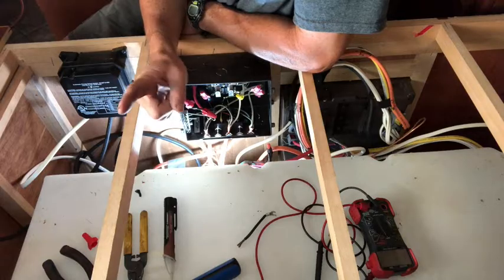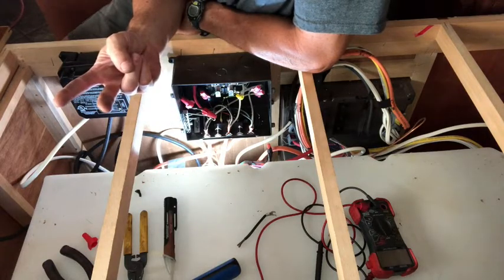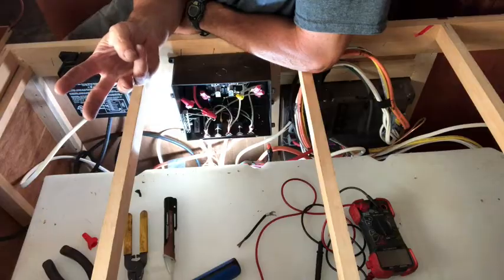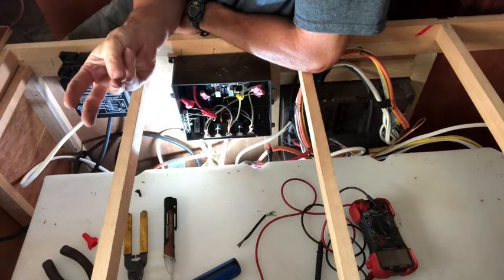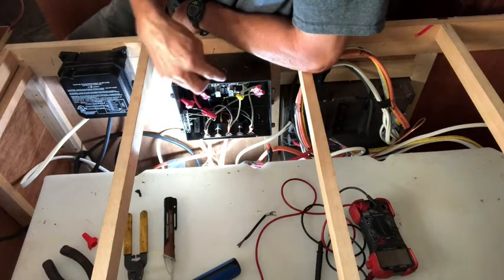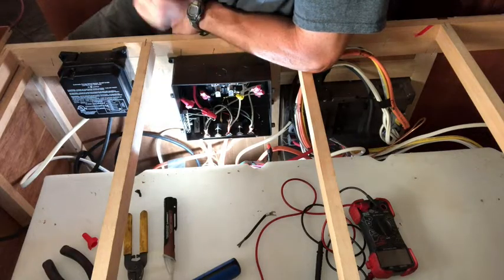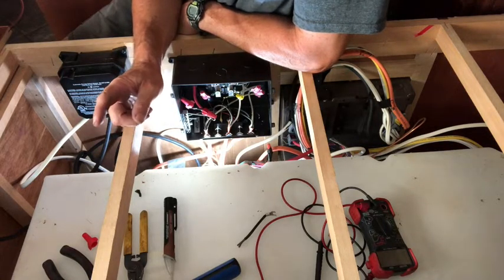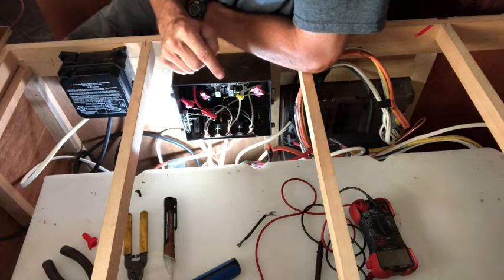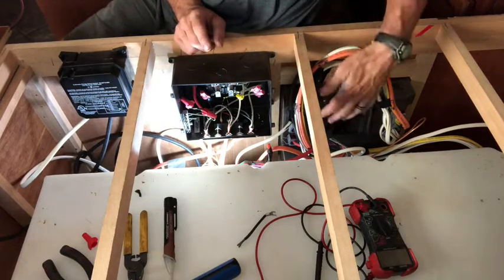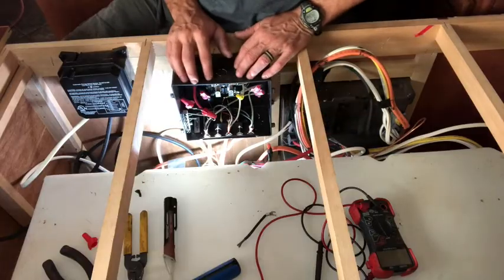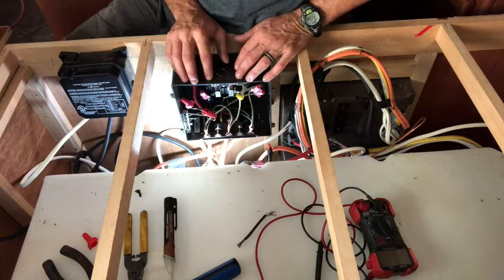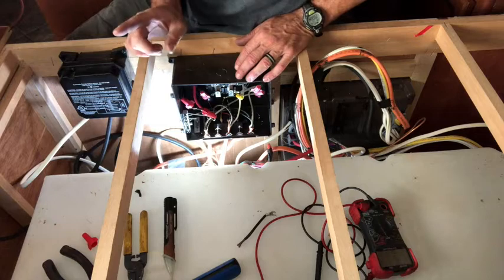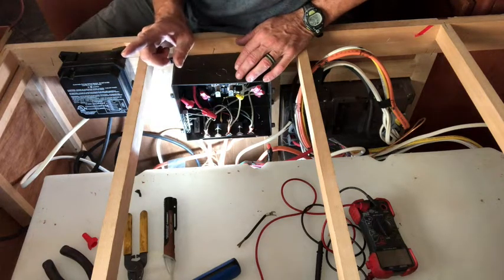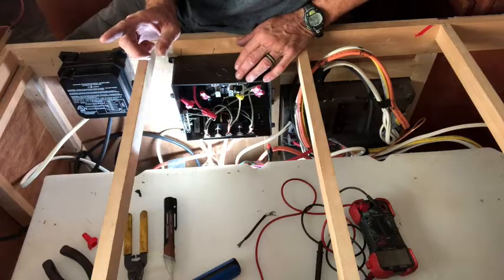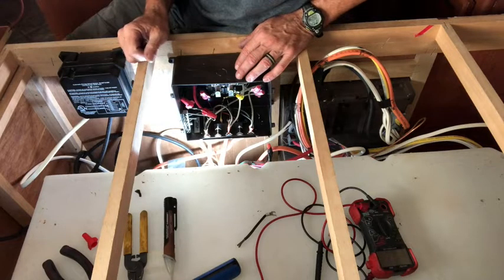Unplug the rig and make sure your generator's not on. If you have a solar system, make sure that inverter is turned off so you're not piping power into your transfer switch. Then think about your batteries too. Generally you won't get any feedback since battery power stops at the fuse box and doesn't come into the transfer switch, because that's 12 volt power. But I know my batteries are dead, so I'm going to throw that fuse anyway. I'm going to unplug the rig and then we'll swap out this transfer switch.